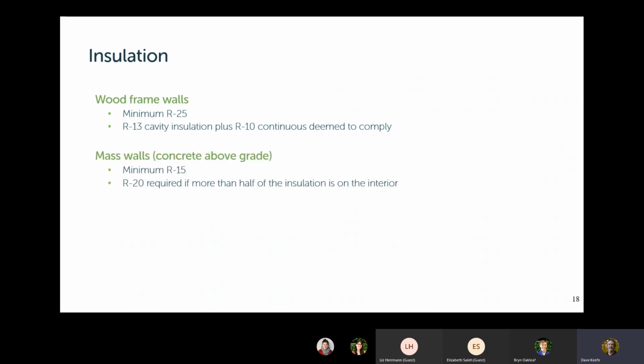For mass walls, which is concrete walls above grade, so this is not basement walls, it's also not log walls. This is concrete above grade. The minimum is R15, assuming that at least half of the insulation is on the outside of the concrete. If more than half of it is on the inside, then you need at least R20. That's assumed to be continuous insulation. For floors, minimum R30, that's floors over outside space.